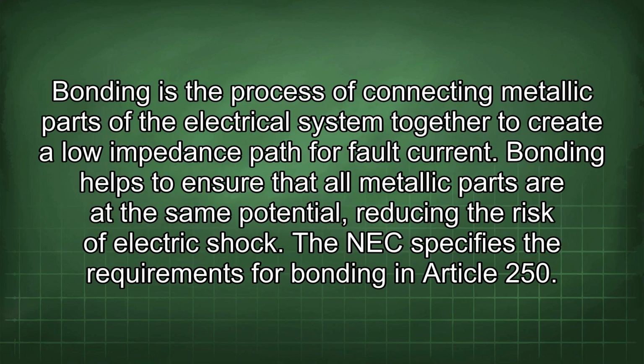Bonding is the process of connecting metallic parts of the electrical system together to create a low-impedance path for fault current. Bonding helps to ensure that all metallic parts are at the same potential, reducing the risk of electric shock. The NEC specifies the requirements for bonding in Article 250.